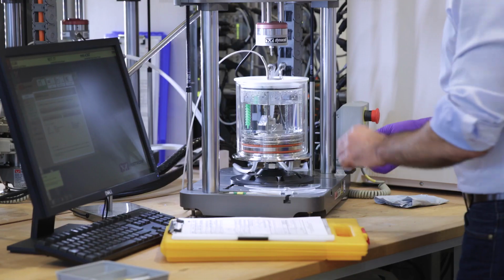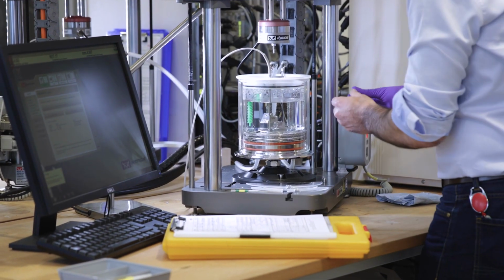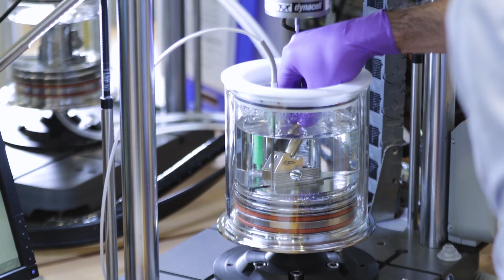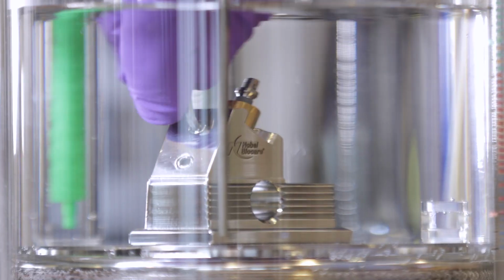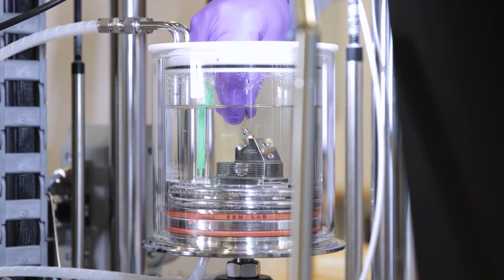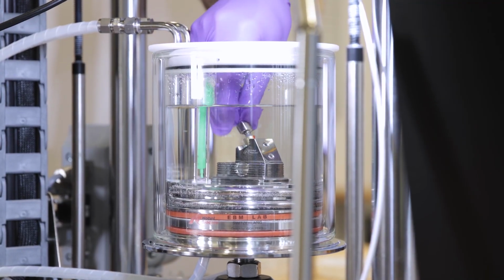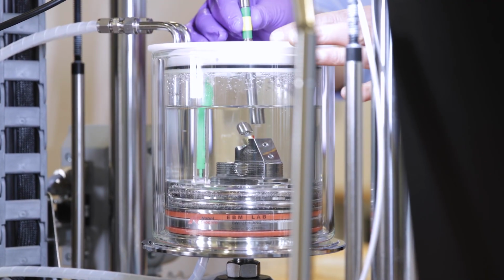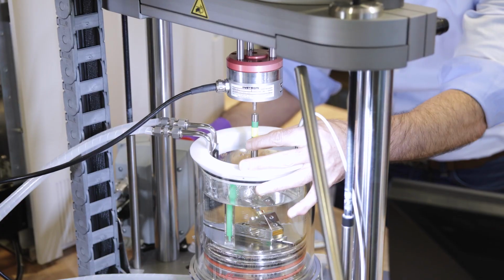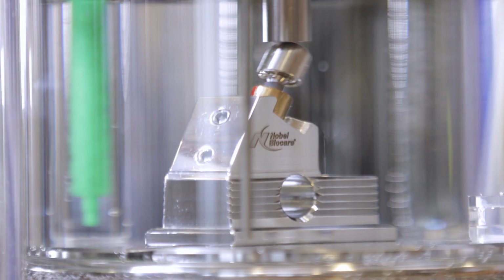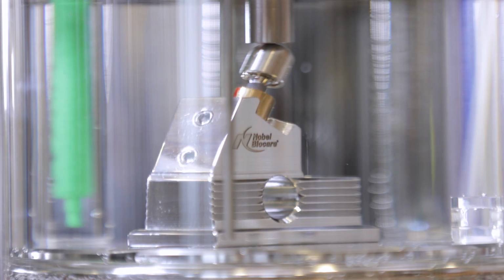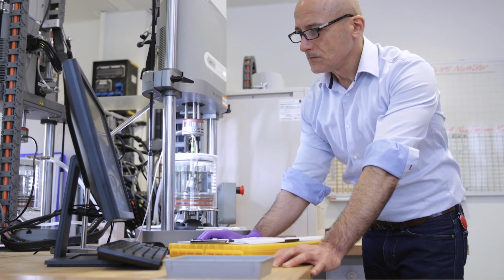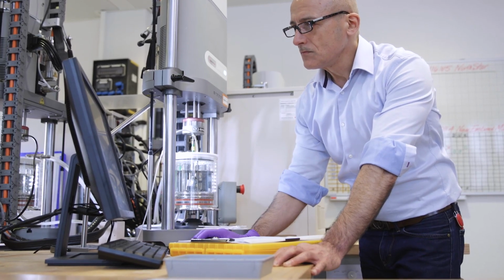The test is performed according to the test protocol. The specimens are tested on the worst case conditions in a water bath with circulating saline solution at 37 degrees Celsius. The test progress is continuously monitored. After the test, the specimen is carefully disassembled and release torques are documented.